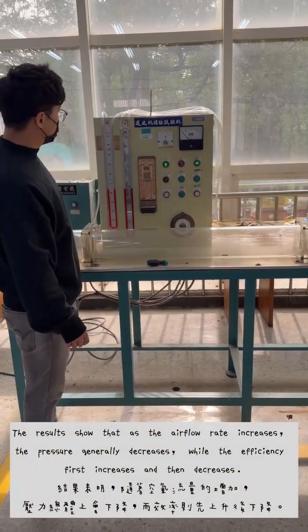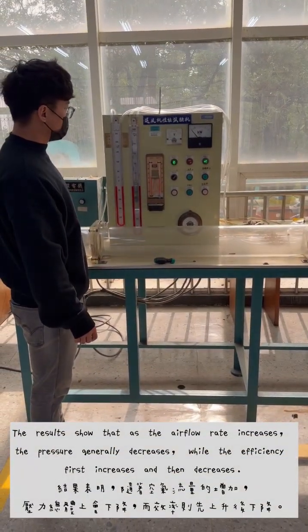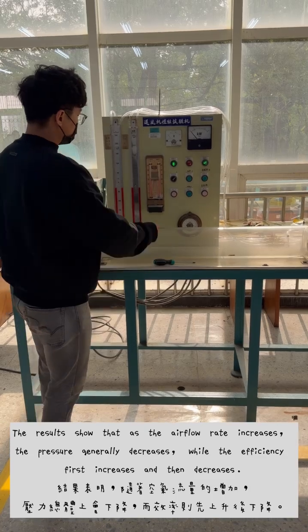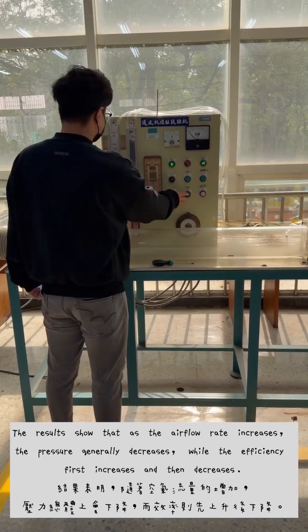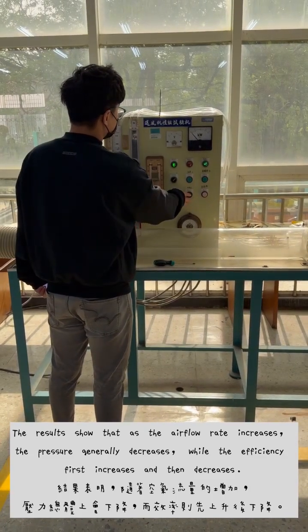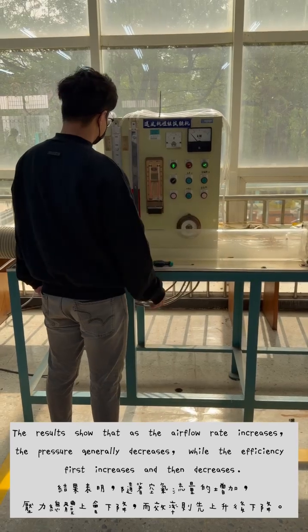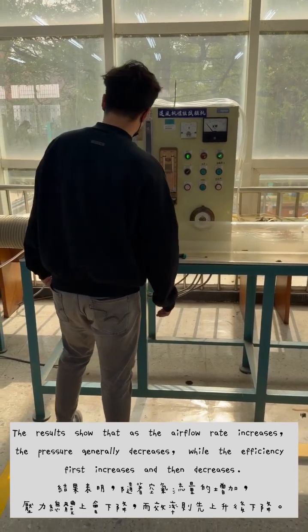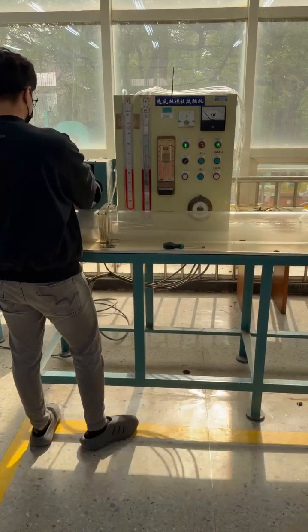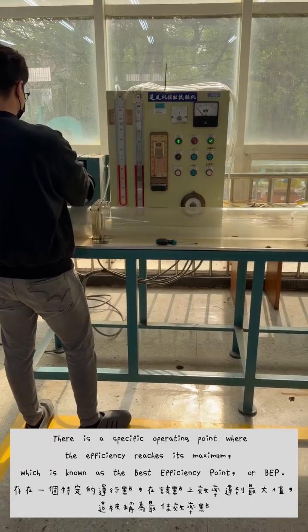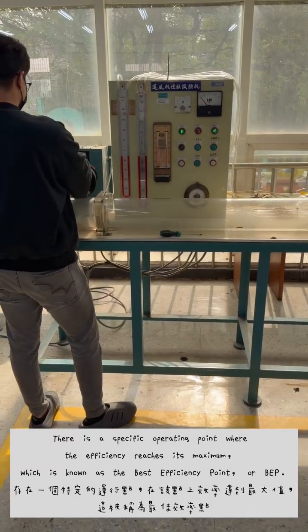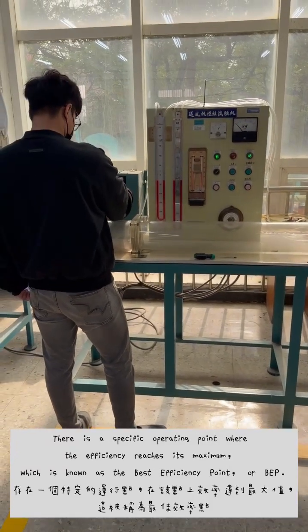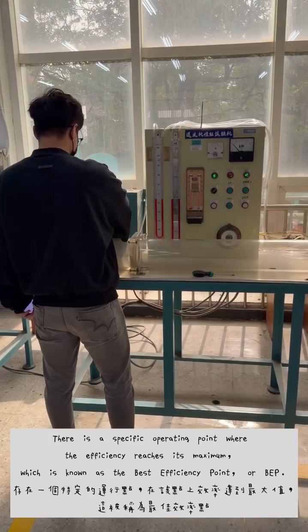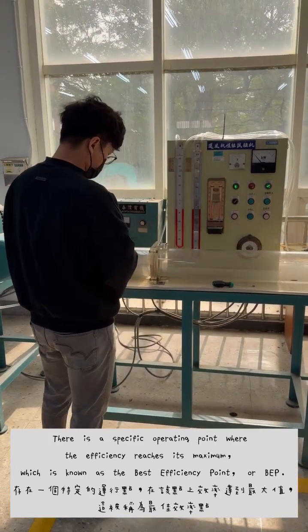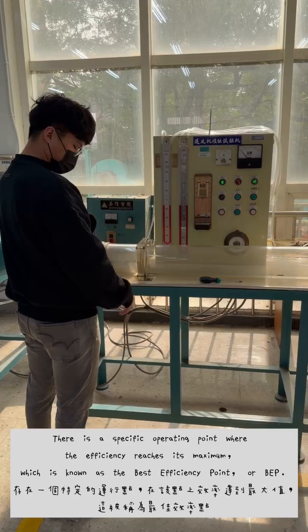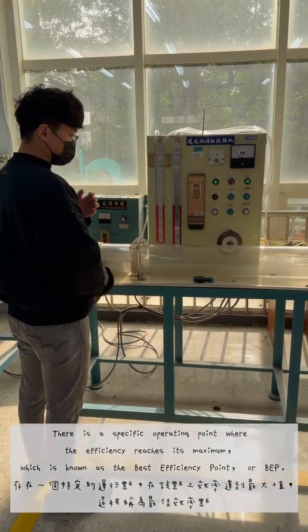The results show that as the airflow rate increases, the pressure generally decreases, while the efficiency first increases and then decreases. There is a specific operating point where the efficiency reaches its maximum, which is known as the best efficiency point, or BEP.